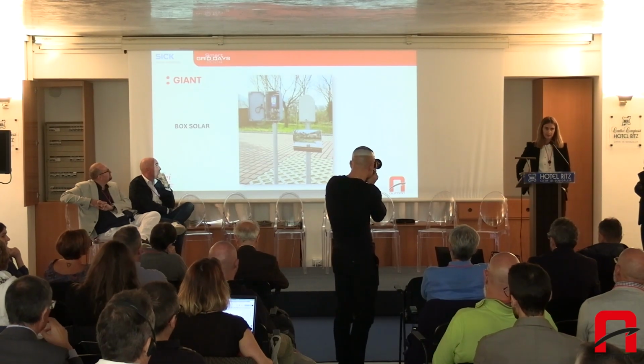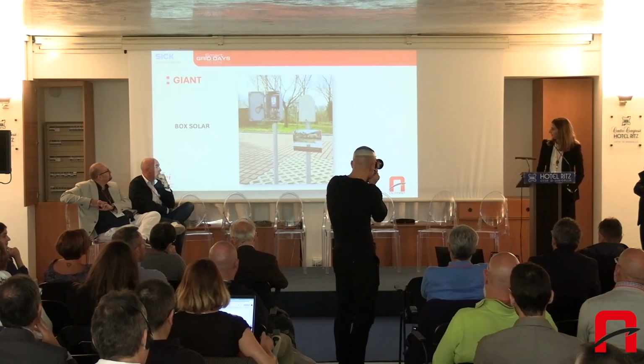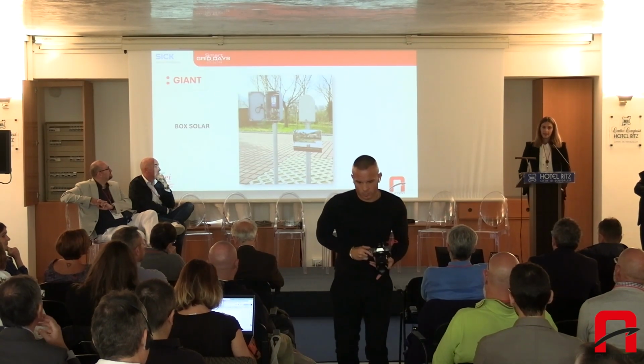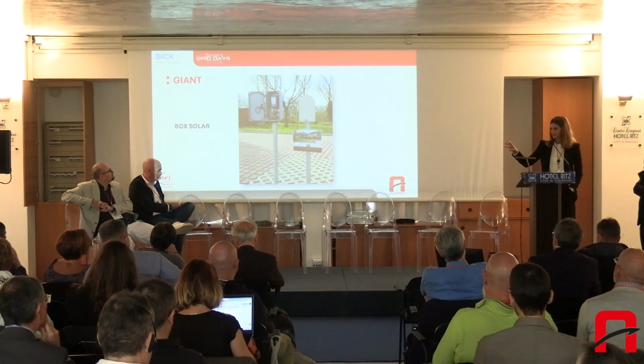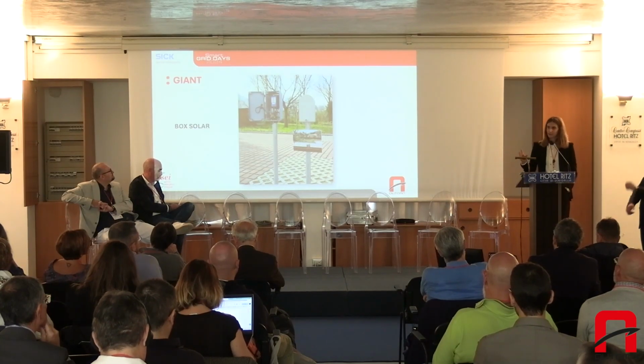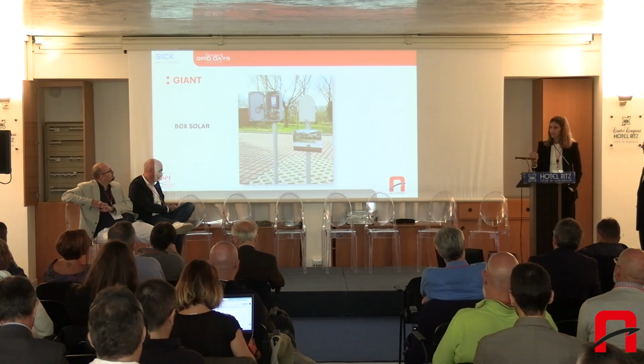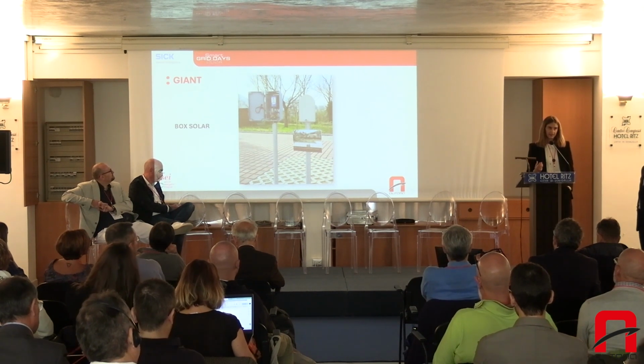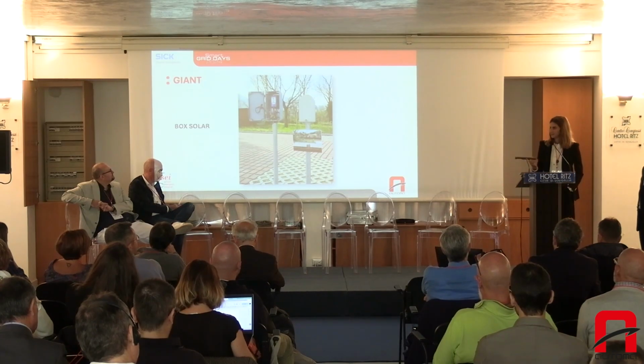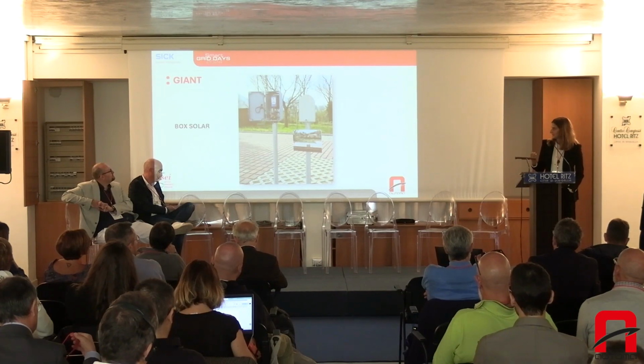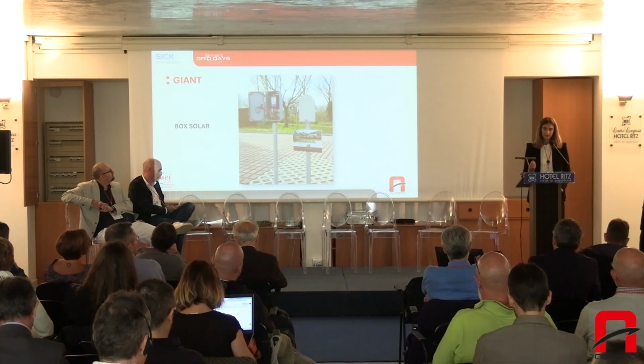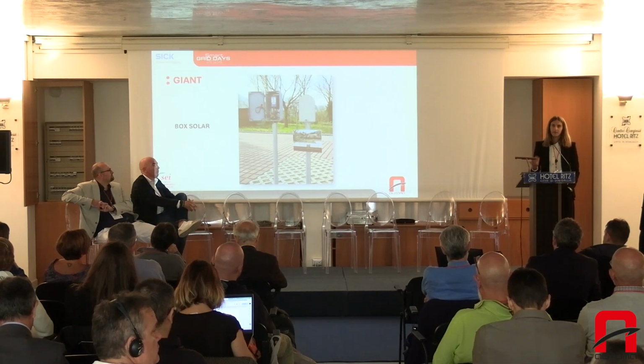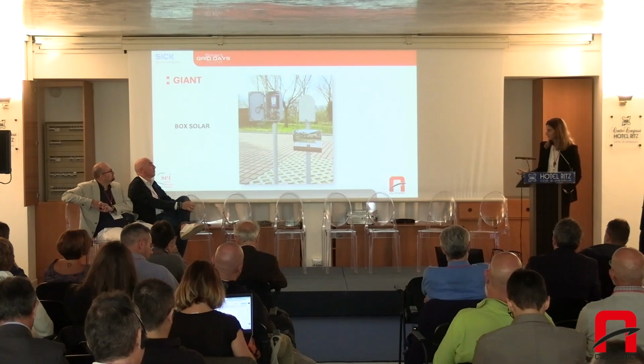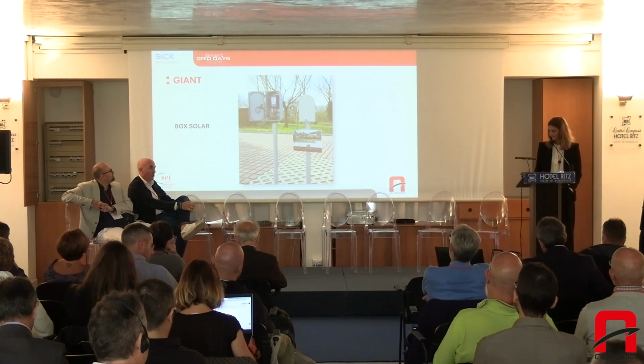One case is open there, but on the other side you see there is a solar panel enabling these devices to work in high power mode and always be accessible. That is because we start from the devices and then have a system in which we can make decisions, based on measurements that come from the field. So any variation in pressure or cathodic protection values forces us to have devices that are always accessible, and in case of an anomaly, to send a warning. This would not be possible if we used a battery system.